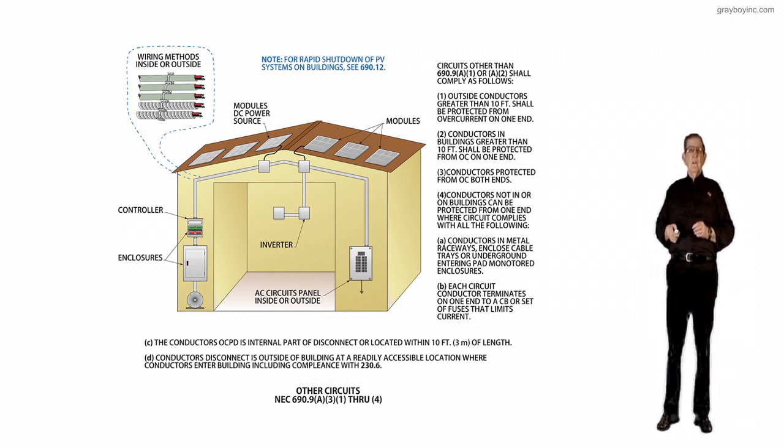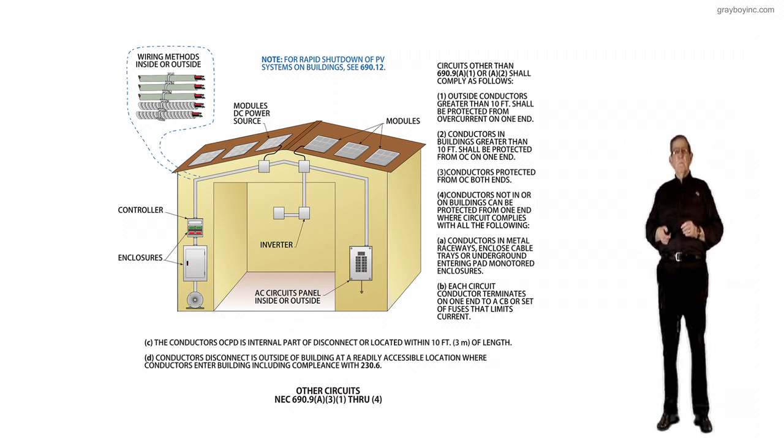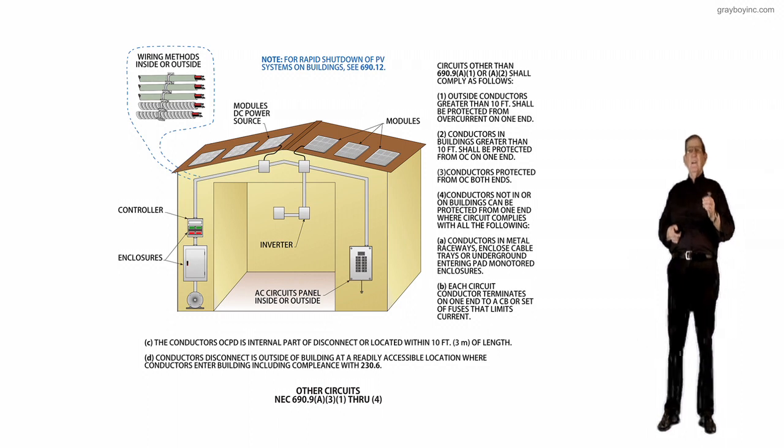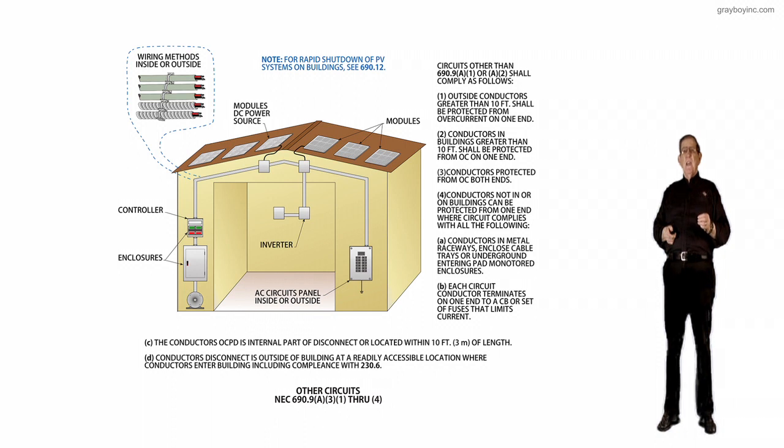And the conductors overcurrent protection is internal part of the disconnect or located within 10 feet of length. D: conductors disconnect is outside of building at a readily accessible location where conductors enter building.